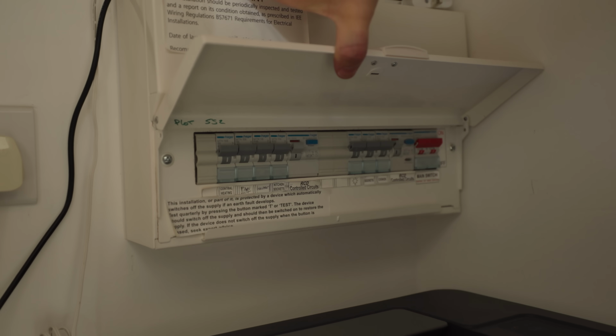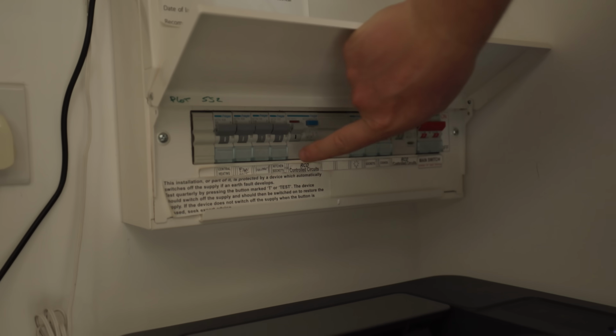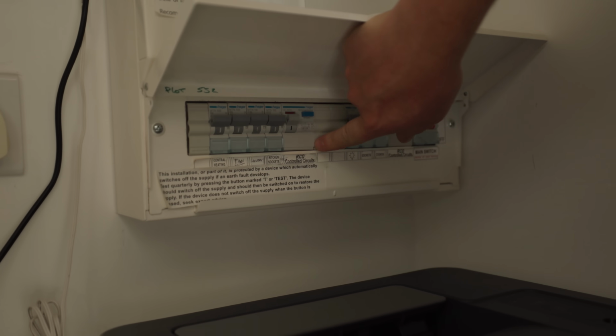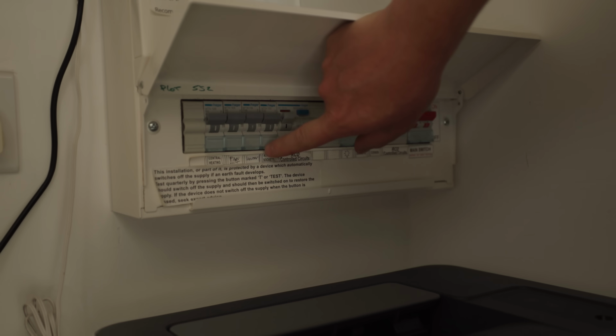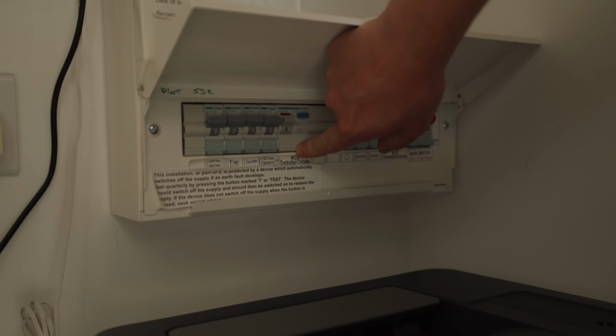We can see the kitchen sockets are fed from this RCD. We're going to have to check whether it's a type A or type AC, and whether it's capable of feeding power back through it. So these are actually type AC RCDs.